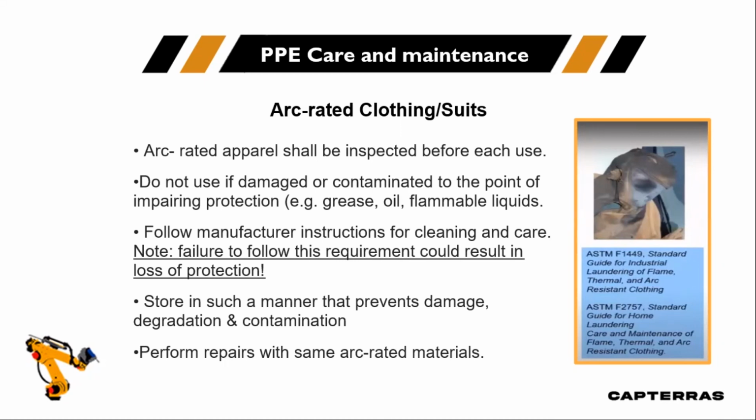As you can see in the picture, here we have an arc rated suit that is already damaged, and we must not use it again.